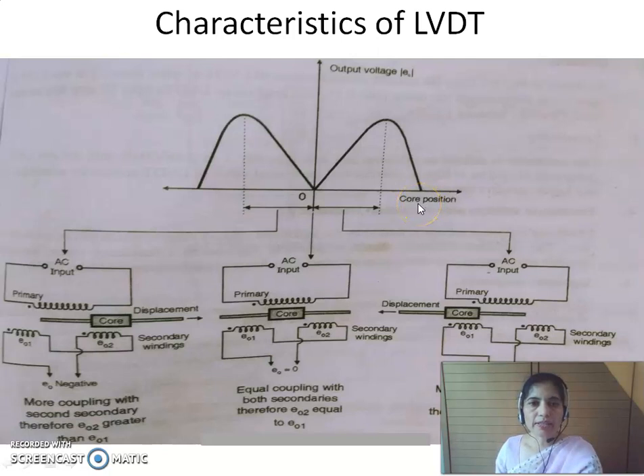As we can see in this portion, which is marked with the red arrow, as well as in this portion of the characteristic, as well as this portion, that is the third, and this. If you look at these four regions of the characteristic, it is almost a linear relation between the output and the core position, except for this curvature where it is a non-linear relation. But the major part of the characteristic of LVDT is linear. That is, the output voltage is linearly proportional to the position of the core.